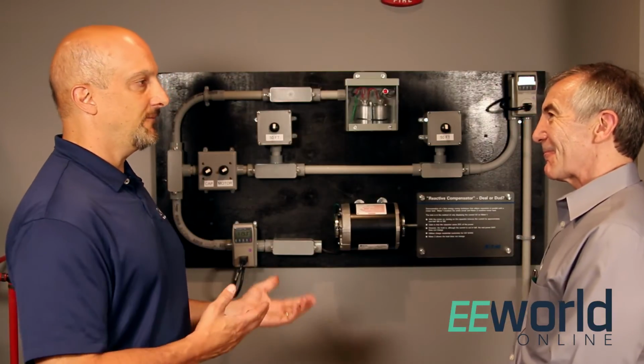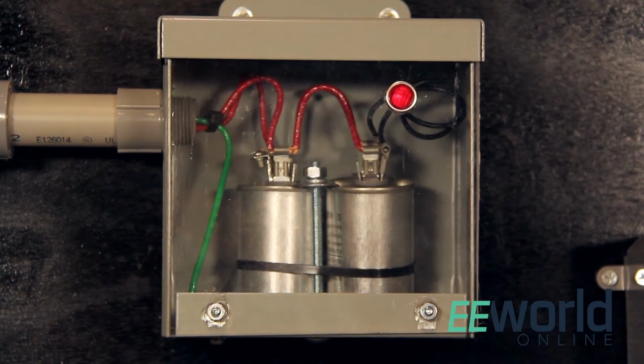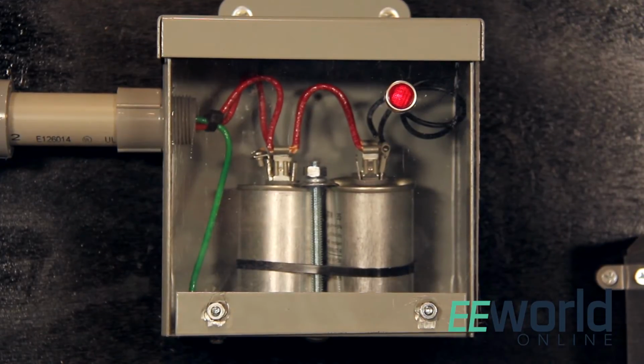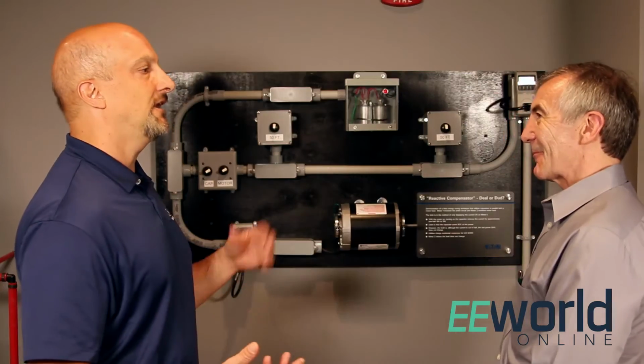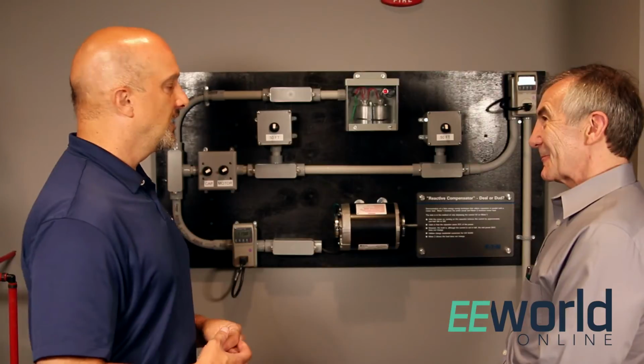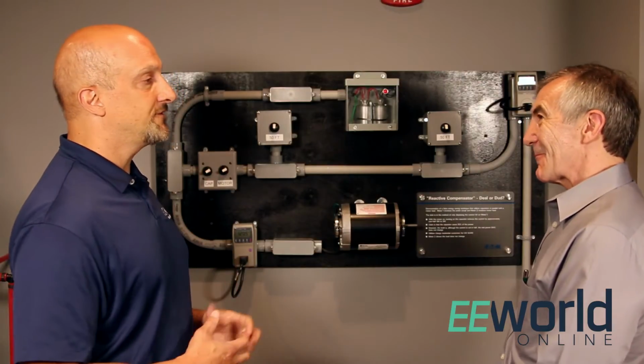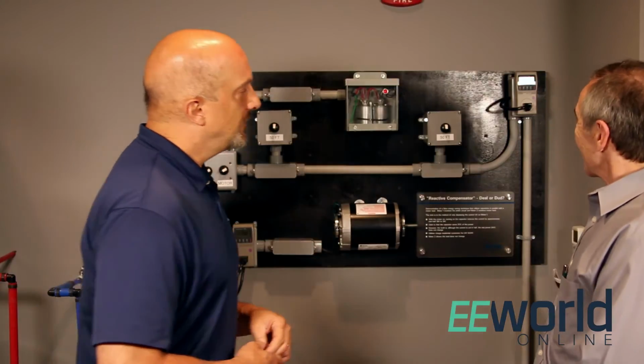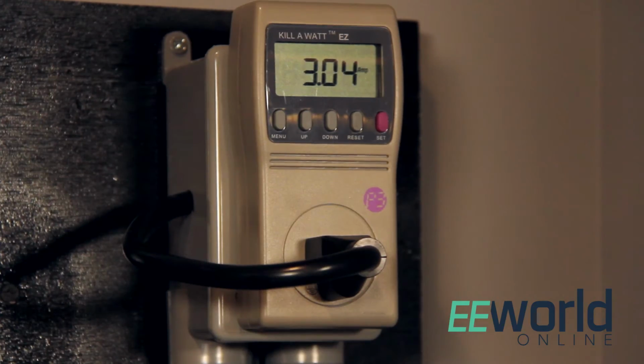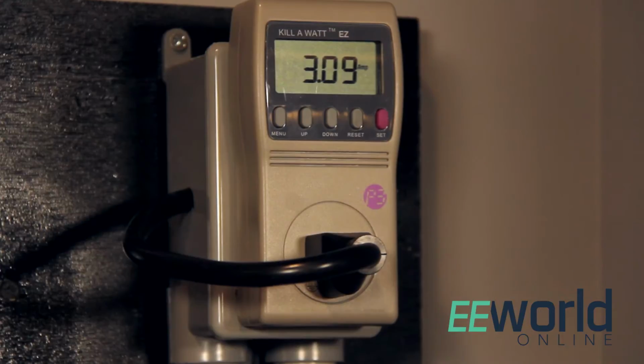From a layman's standpoint, people think volts times amps equals watts, but it's really volts times amps equals volt-amps, which has two components: watts and reactive power, or kVAR, that supplies power to the motor. Those two make up the VA or kVA. So when you look at the meter and see the amps went down, you might automatically assume the watts went down.